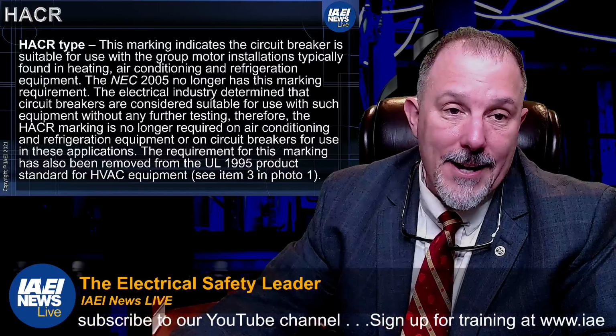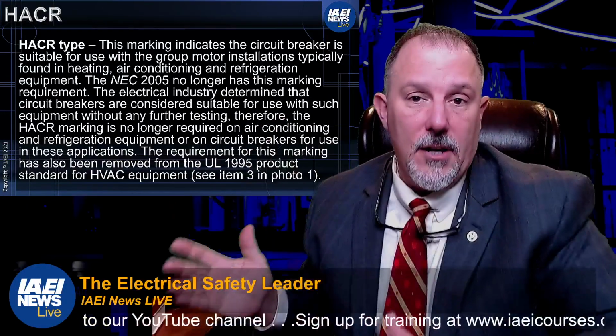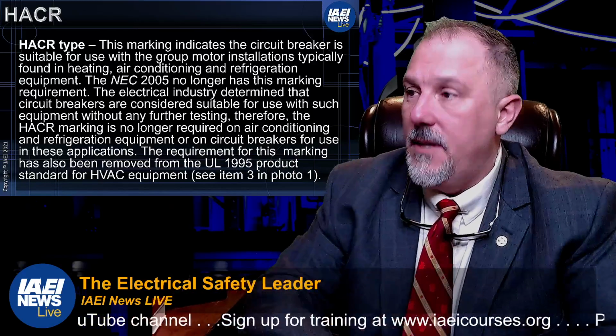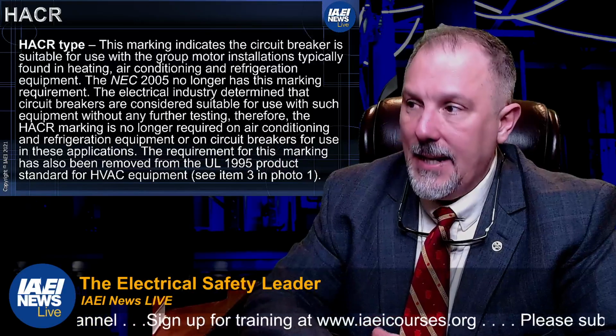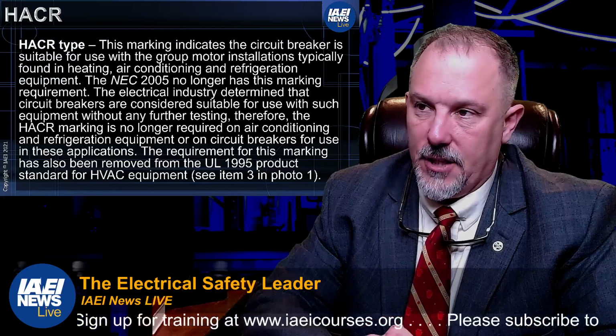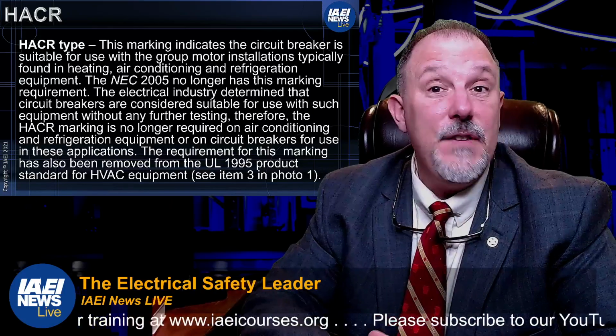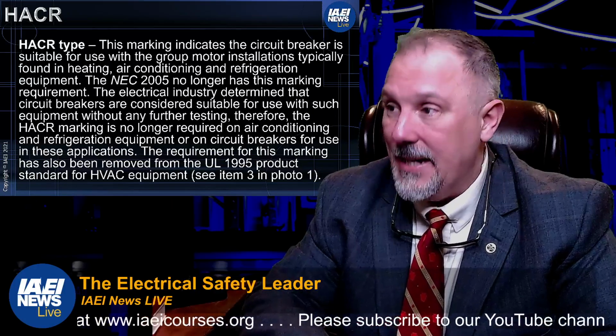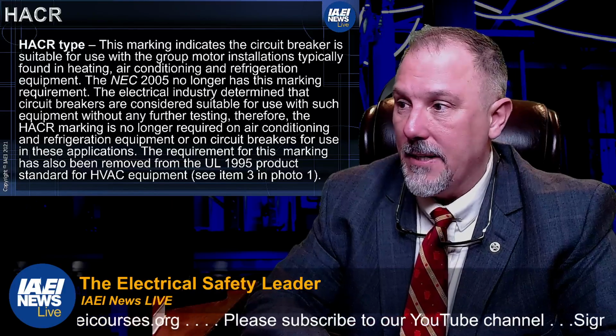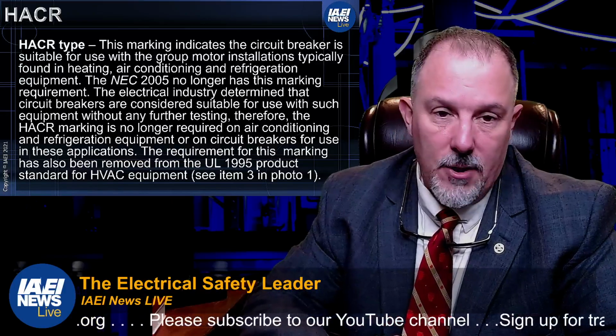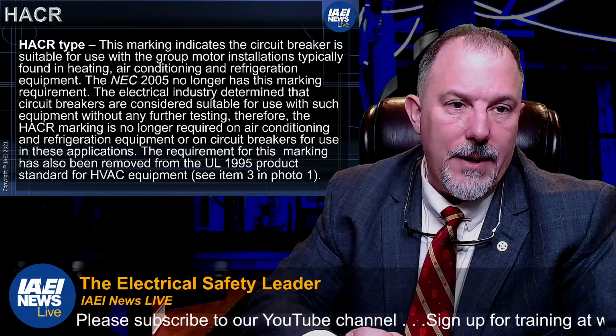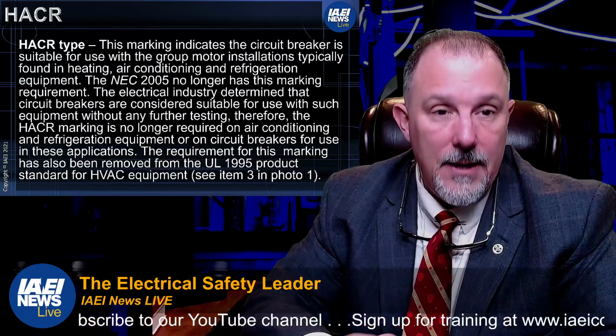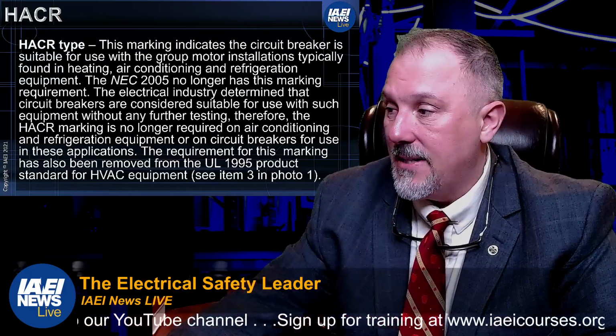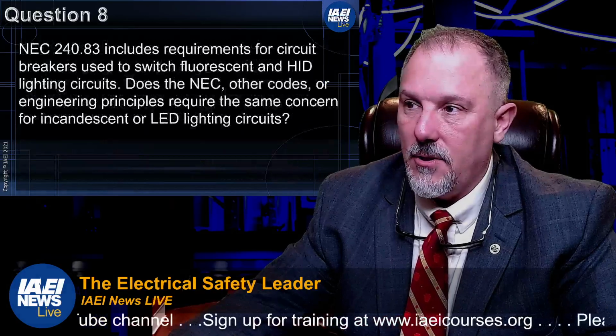All right, so HACR rated. Now that's another marking you'll find on a circuit breaker. This is your heating, air conditioning, and refrigeration, not ventilation. HV, the V is missing. So it's heating, air conditioning, and refrigeration equipment. It no longer has a marking requirement in that regard. And I know it doesn't have anything to do with lighting, but this is another marking that you may see, but it's no longer used.